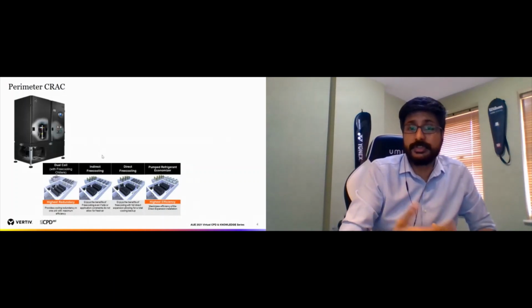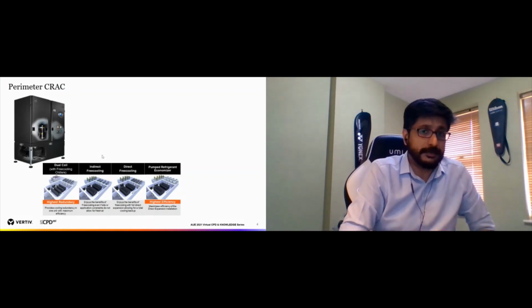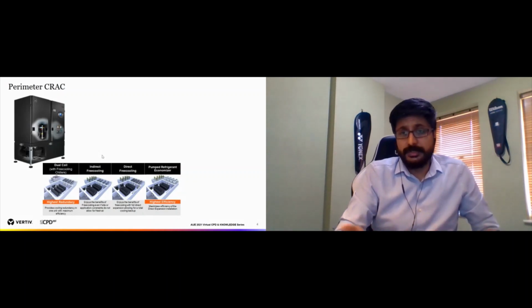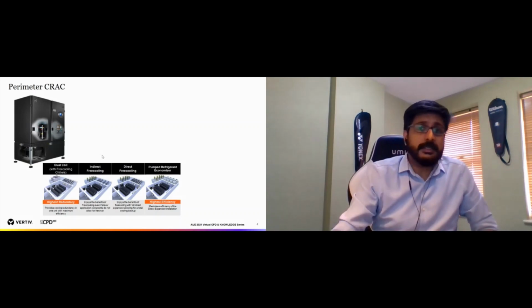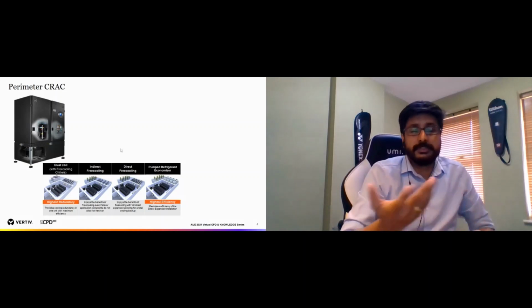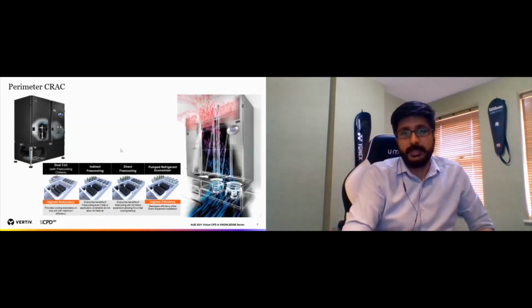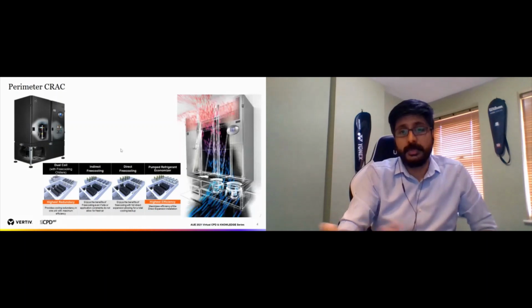And to increase the efficiency, we have the pumped economizer system on those units as well. So that's a traditional DX cooling, or the perimeter DX cooling. The difference with the chilled water system is that instead of the DX, you'll have a chilled water coil in there, and the water is cooled outside by using a chiller.